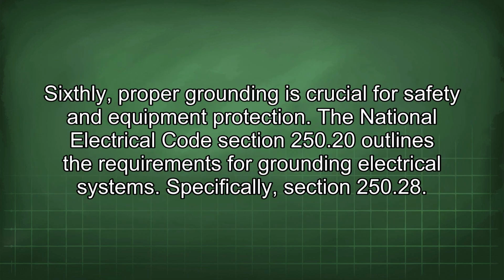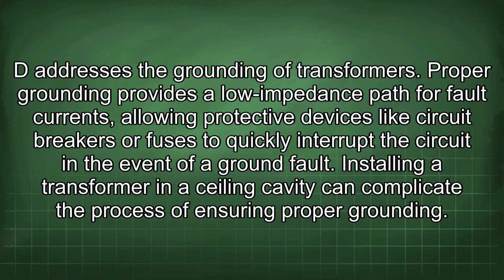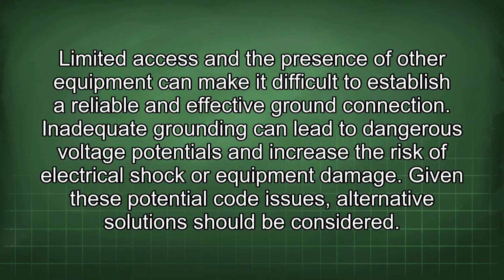Sixthly, proper grounding is crucial for safety and equipment protection. The National Electrical Code Section 250.20 outlines the requirements for grounding electrical systems. Specifically, Section 250.28(d) addresses the grounding of transformers. Proper grounding provides a low-impedance path for fault currents, allowing protective devices like circuit breakers or fuses to quickly interrupt the circuit in the event of a ground fault. Installing a transformer in a ceiling cavity can complicate the process of ensuring proper grounding. Limited access and the presence of other equipment can make it difficult to establish a reliable and effective ground connection. Inadequate grounding can lead to dangerous voltage potentials and increase the risk of electrical shock or equipment damage.